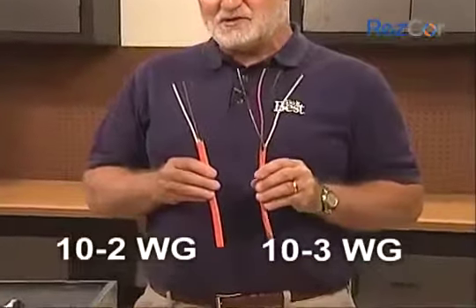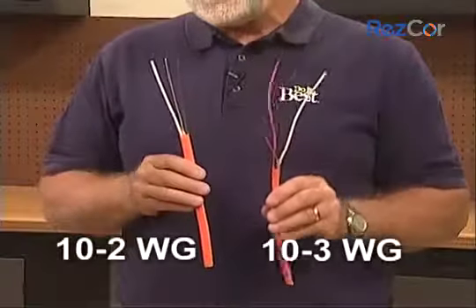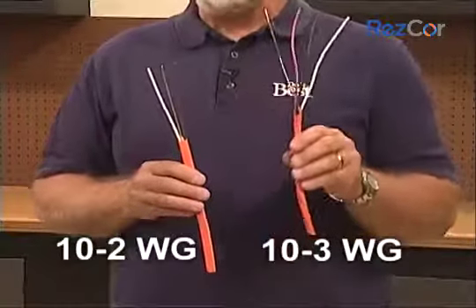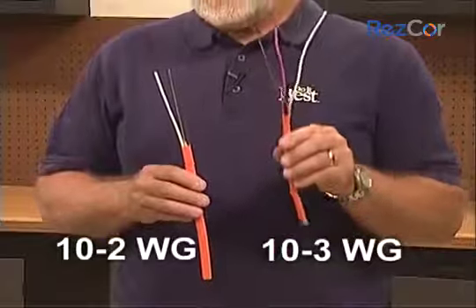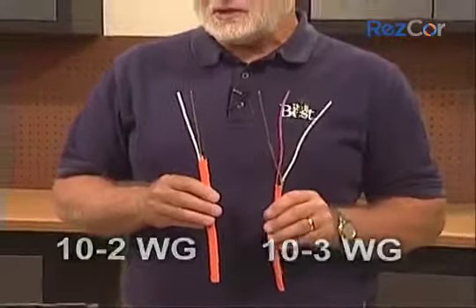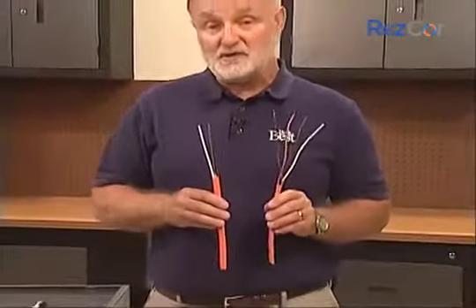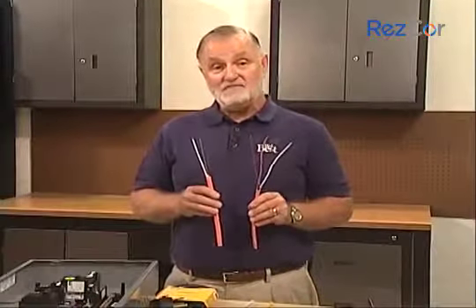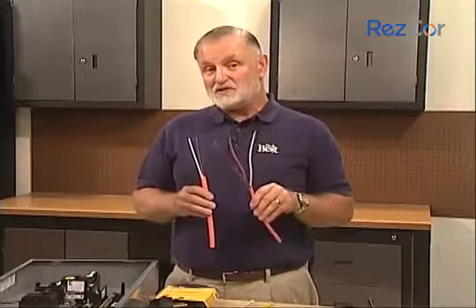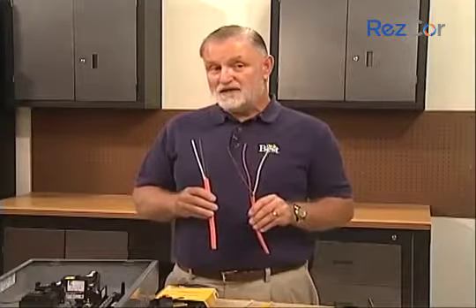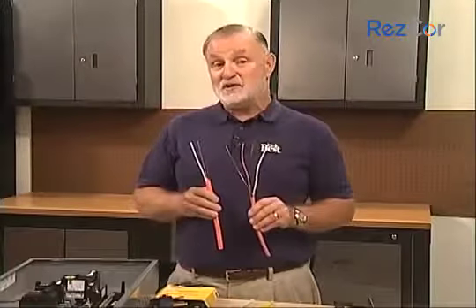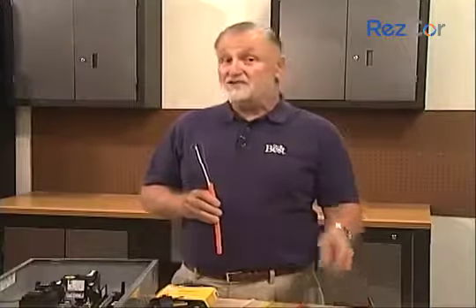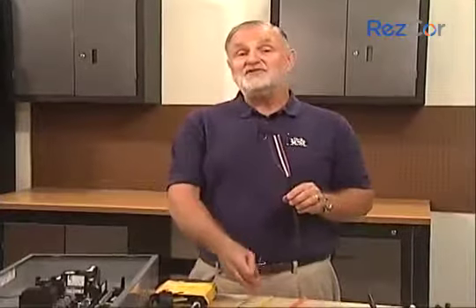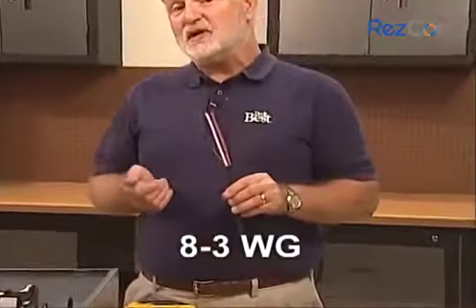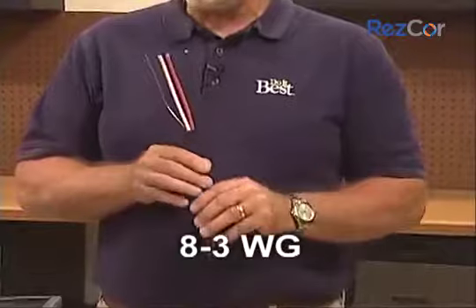The 10-2 cable is used for electric water heaters, while 10-3 cable is most commonly used for electric dryers and cooktops. Be careful about what you suggest for a cooktop, because manufacturers have recently begun making a type of cooktop that has 5 burners instead of 4. It looks like 4 burners, but one is a dual burner, counting as 2. That type of cooktop takes 8-3 with ground cable, not 10-3. Cable rated as 8-3 with ground is often sold for regular electric ranges, but I don't recommend it.